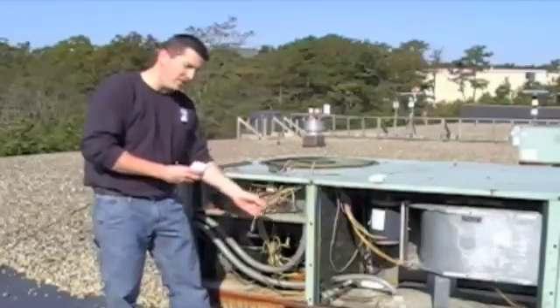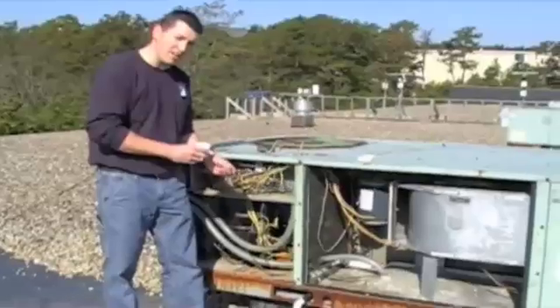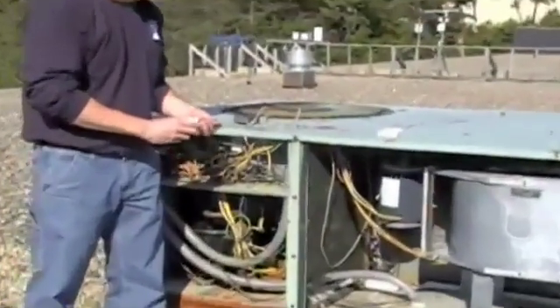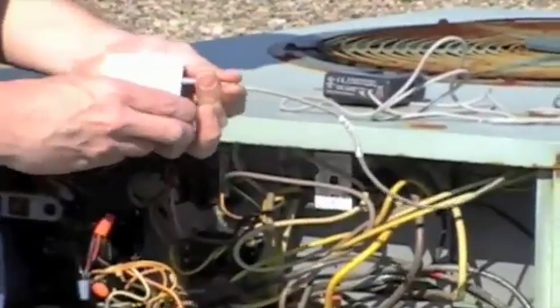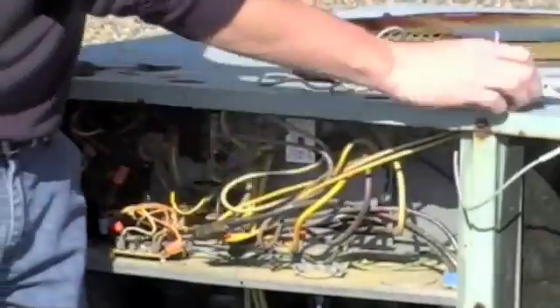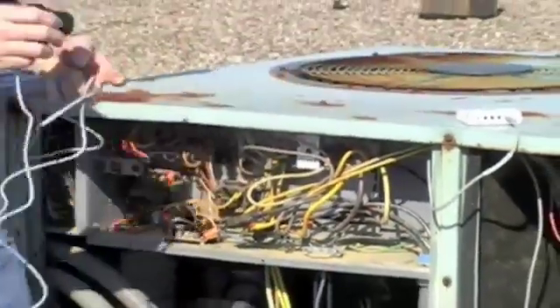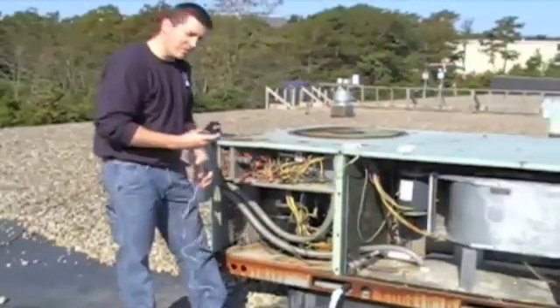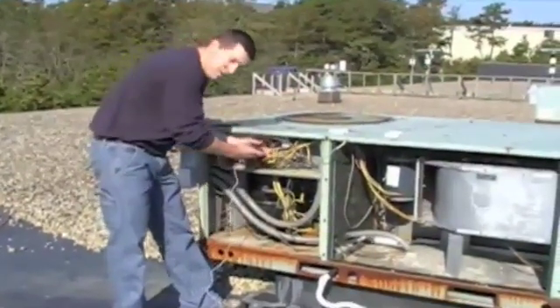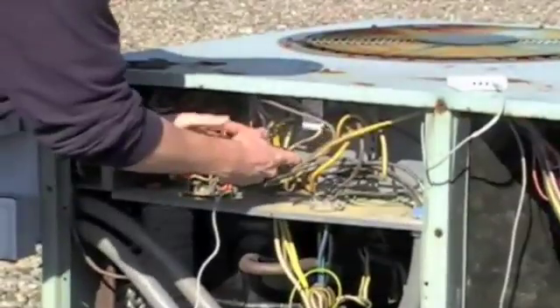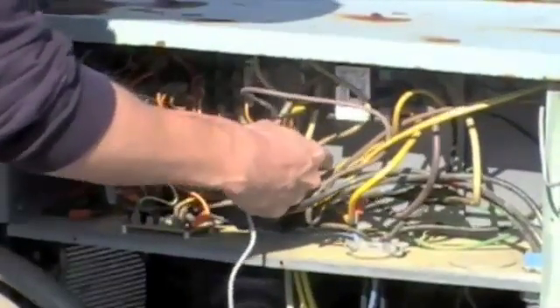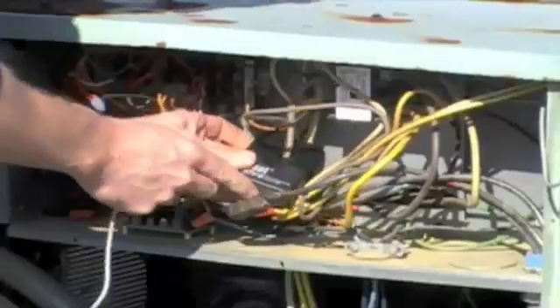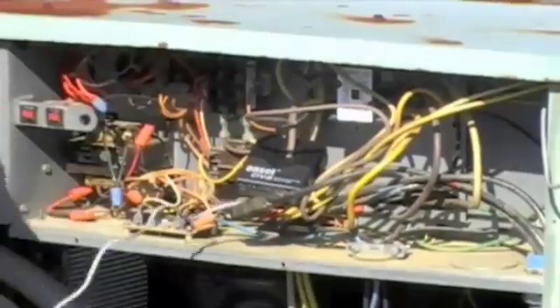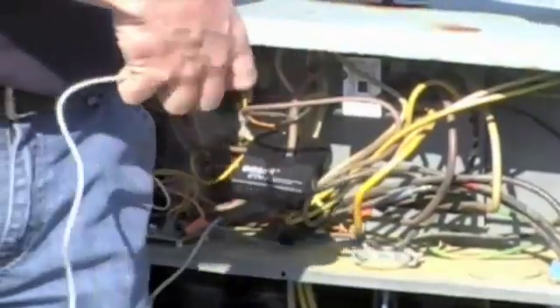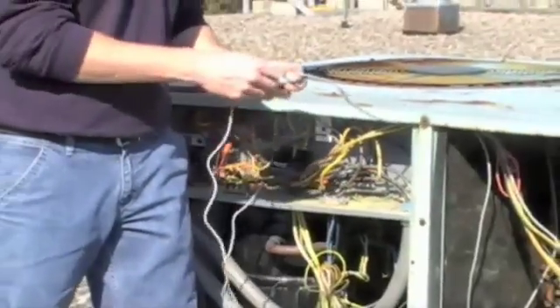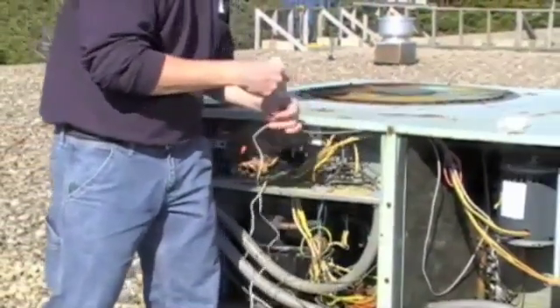And what we've done is we've run our temperature probe through the unit into the supply duct on the other side of the unit. And we're going to plug this into channel 1 on the logger, which has been set up to read the temperature. And we're going to take our amp probe, and we're going to measure our compressor amperage with this. We're going to clip that right onto the wire feeding the compressor. Then we're going to plug that into channel 2, which has been set up for amperage on the logger.